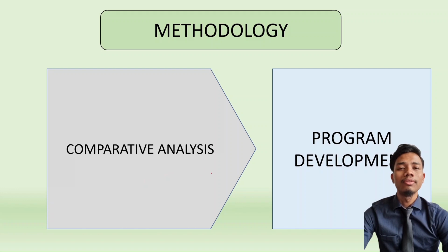For the program development, it is decided to use Microsoft Excel to develop a program that can determine the required pump power for a specific pump design. All the data from HTM-0201 will be brought into the program, as the program is based on the HTM standard.